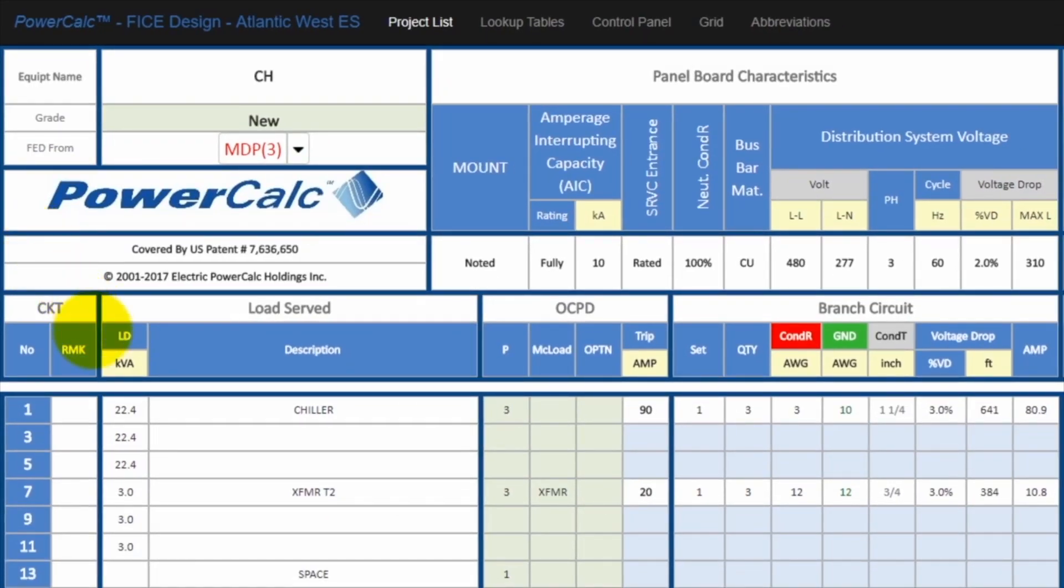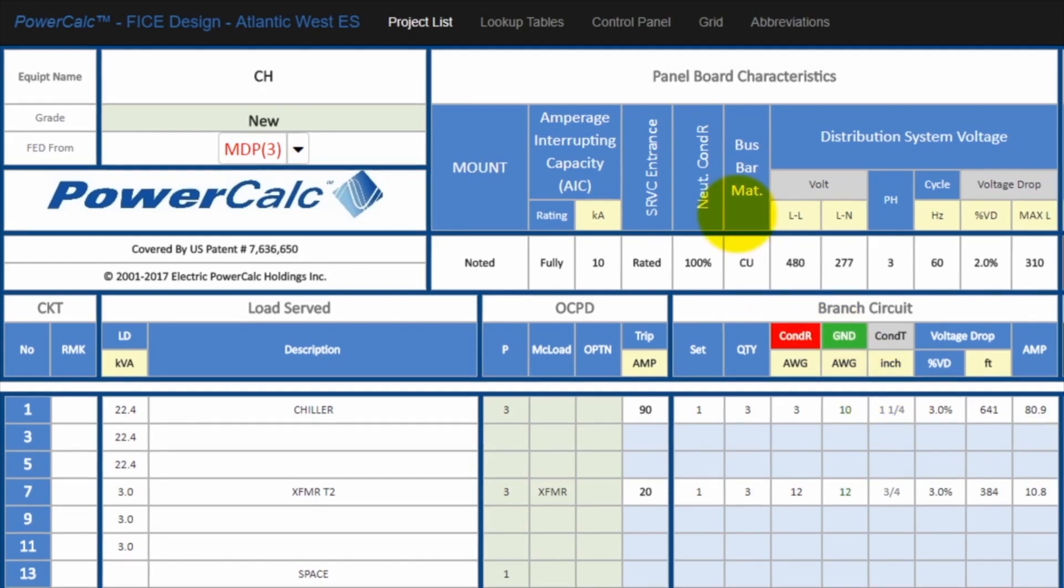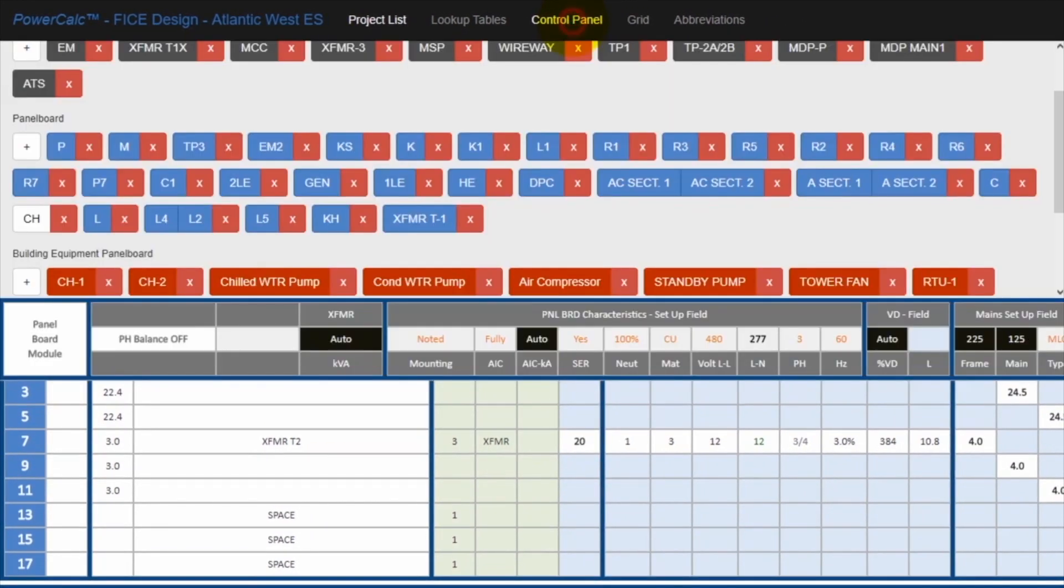And then we see that the circuit associated with the chiller is circuit number one. And it is the chiller and it is the overcurrent protection device associated with that chiller to safely protect it and safely operate. And then the conductor size that we talked about, three number three and a number 10 ground and one and a quarter inch conduit. If you go back to the power distribution network, click on the control panel.